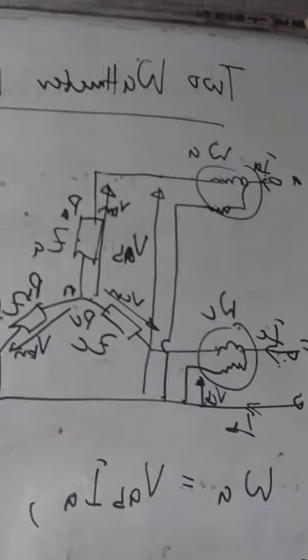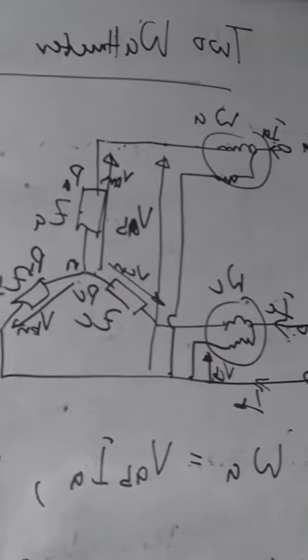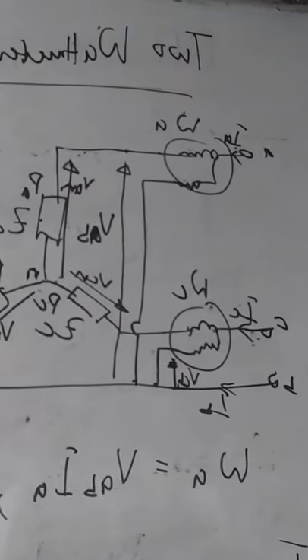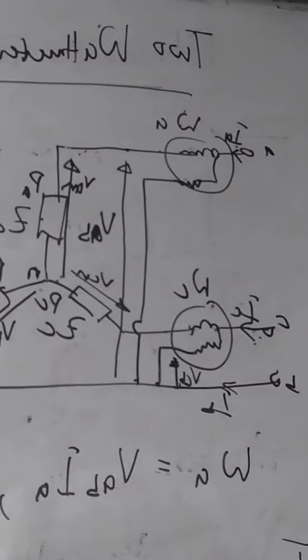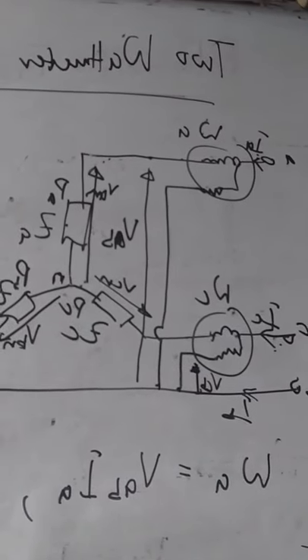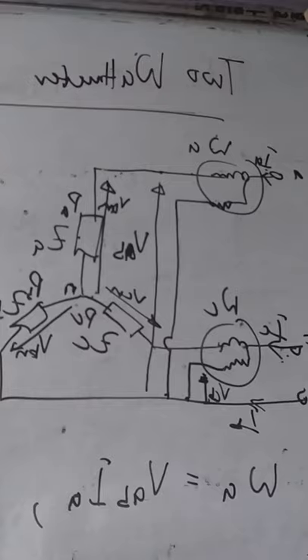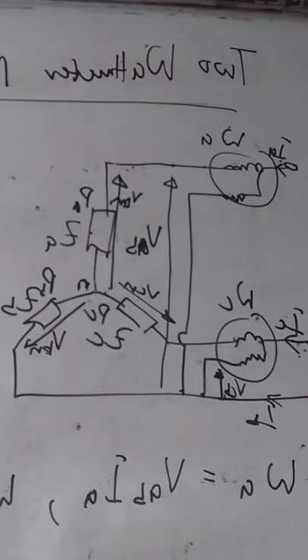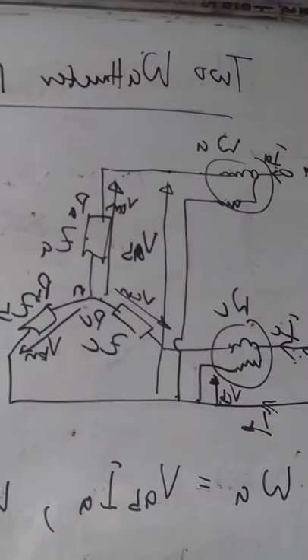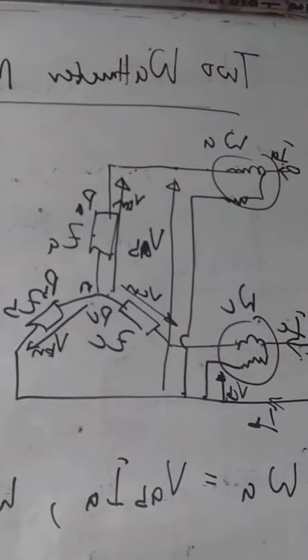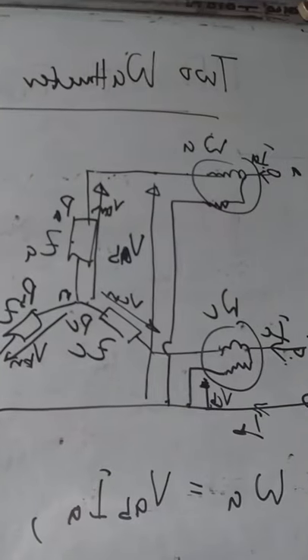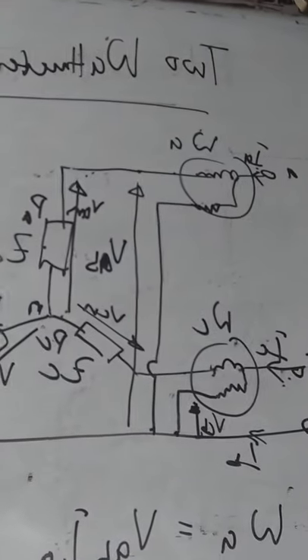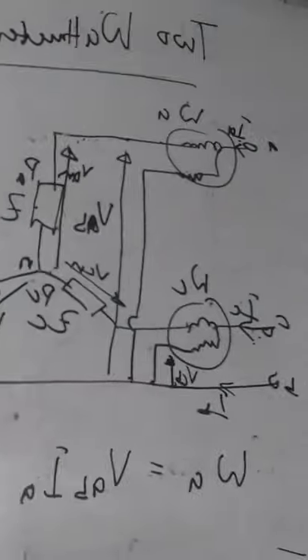The difference lies in the fact that with single watt meter method you can only use it to measure power in balanced systems alone, but with two watt meter method you can use it to measure power in balanced or unbalanced systems, whether it is star or delta connected.